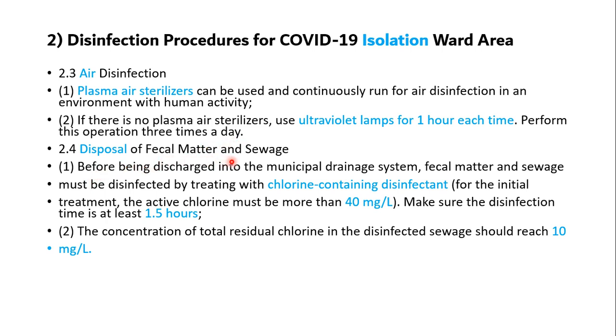Disposal of fecal matter and sewage. Before being discharged into the municipal drainage system, fecal matter and sewage must be disinfected by treating with chlorine-containing disinfectant. For initial treatment, the active chlorine must be more than 40 mg per liter. Make sure the disinfection time is at least 1.5 hours. The concentration of total residual chlorine in the disinfected sewage should be 10 mg per liter.